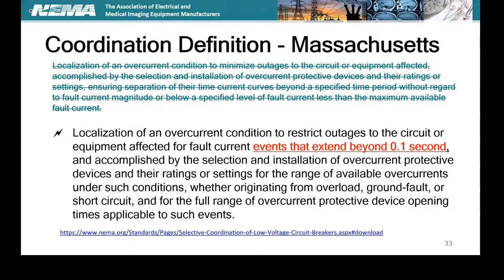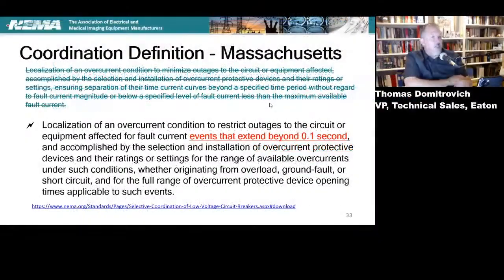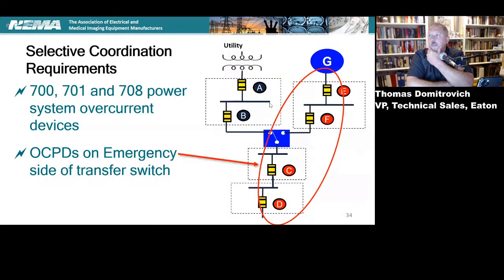So here's the difference between what you're looking at there: what we call the 0.1 second, which to your point was what healthcare did. And what that basically does is, if you look at 700, 701, and 708, you have to evaluate the performance of your system with regard to current, how much current is passing through those overcurrent protective devices. For example, what you're seeing on the screen here, if I have a fault downstream of device D, I need to determine whether or not device C will trip before device D. And if I don't calculate a fault current and compare it to the trip curves, I do not know whether or not device D will trip before device C.